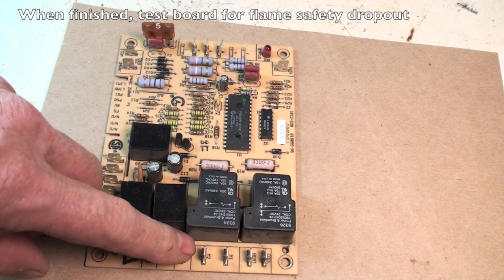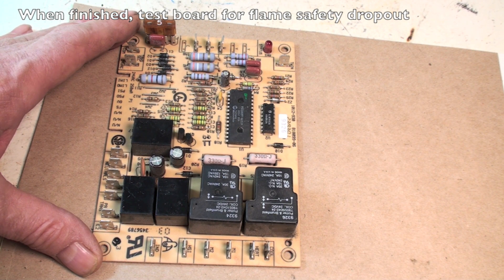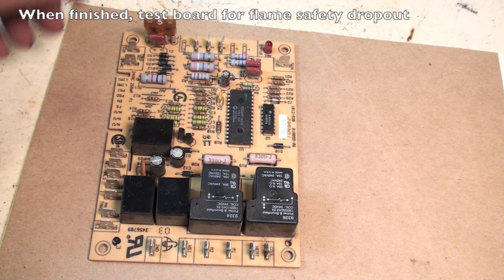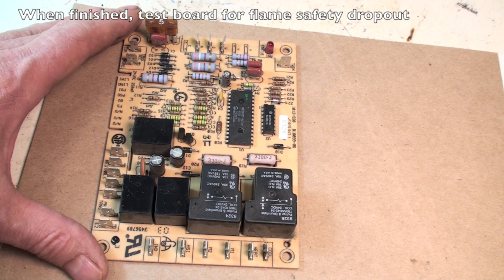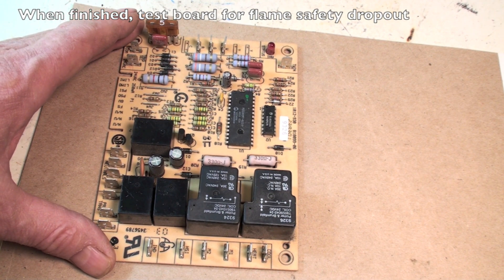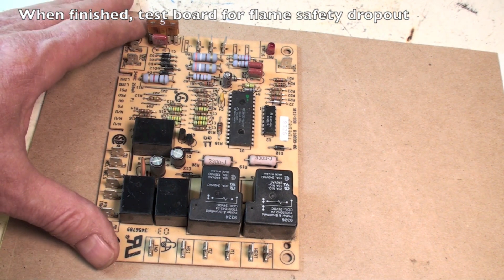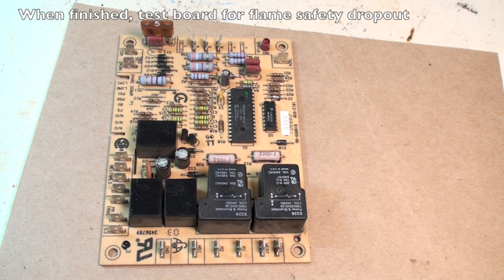The high voltage and 24-volt wiring areas — maybe those — but don't get into any electronics other than possibly fixing a solder joint on a resistor. The board usually tells you where the problem is through some sort of blinking code. Now, if you come onto this board and it's not working and not even blinking a code — maybe just blinking a status light for no call for heat...